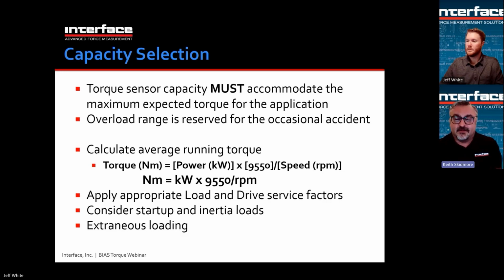They don't typically say how much torque the motor produces on the nameplate, but you can calculate that. If you know the RPM, the speed of the system, and you know how many kilowatts the motor is, you can calculate it. It's kilowatts times 9550 divided by RPM equals Newton meters. What that gives you is the average running torque. Doesn't mean there aren't a bunch of pulses and spikes. That's just what the average running torque is.